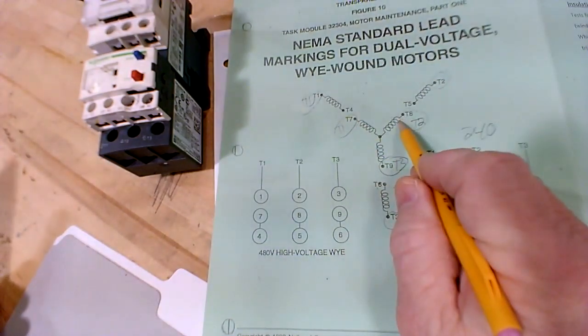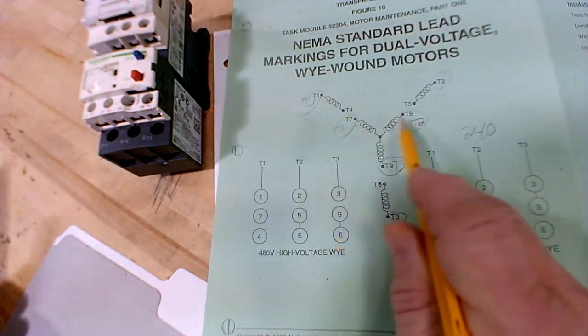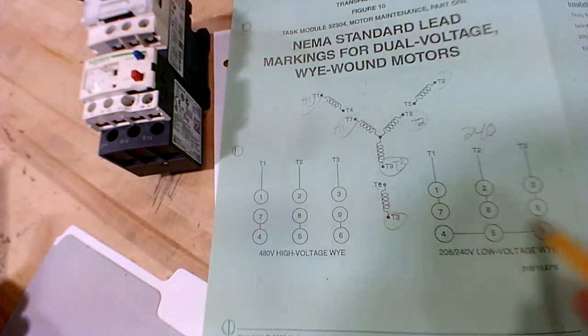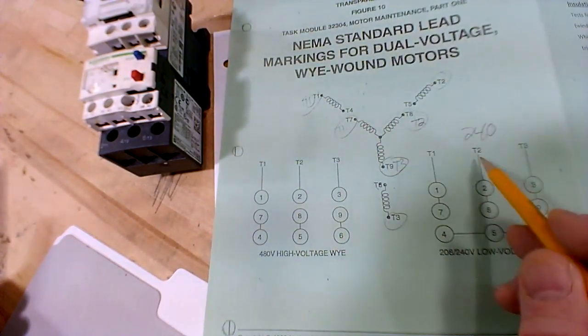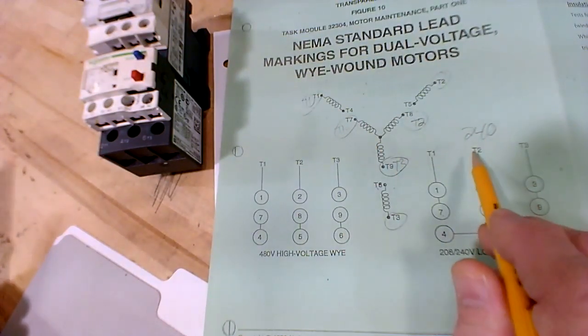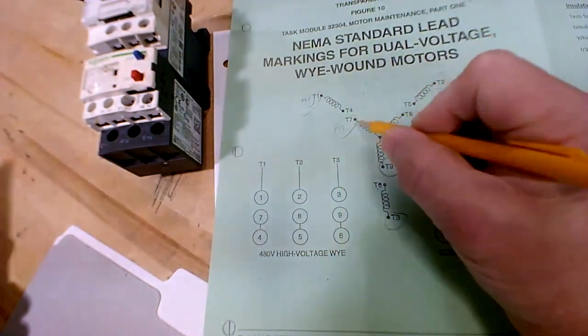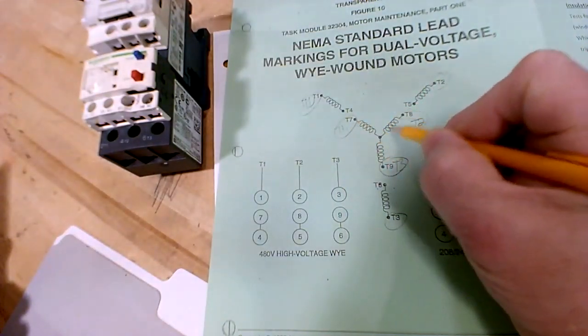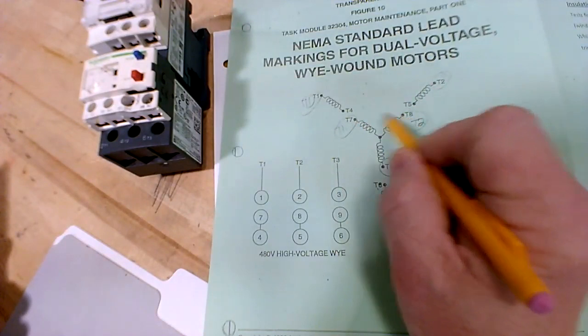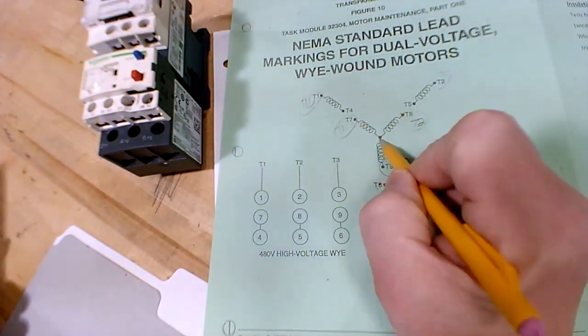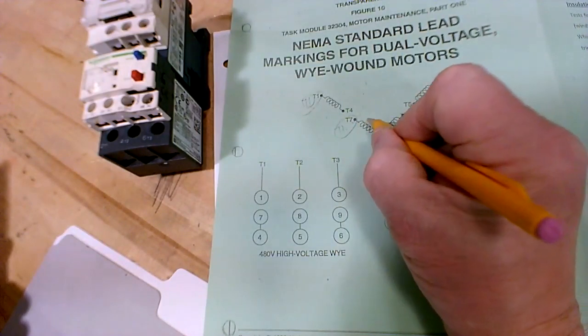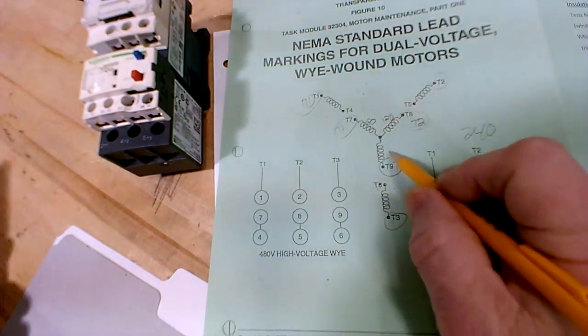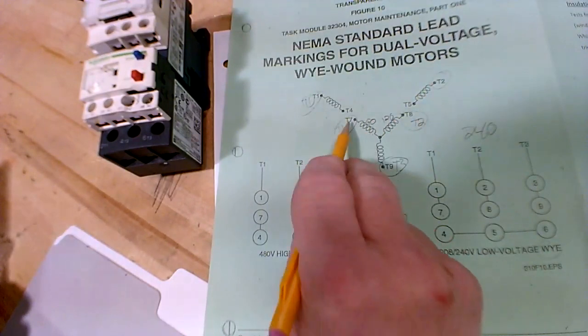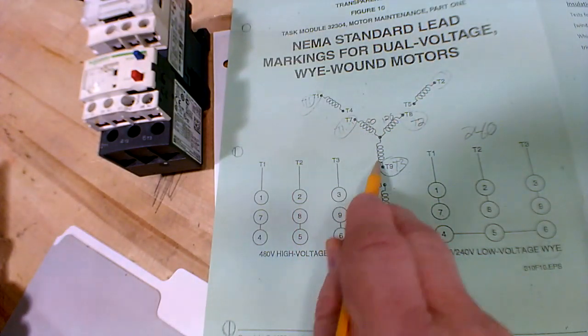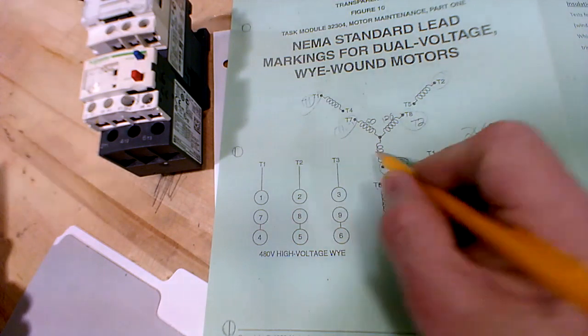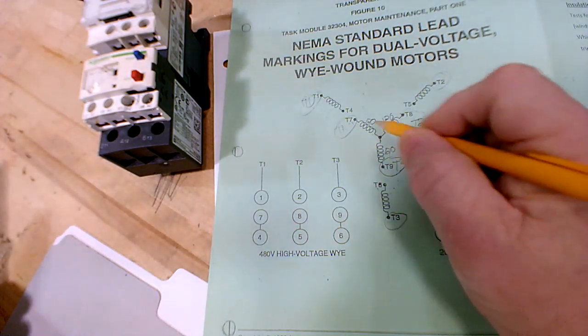So right now, on the inner Y, if I measure from here to here, what will I measure? T1 to T2 on the inner one now, over here. What would I read? 240. I would read 240 across these. Here I've got 2 windings in series. If I've got 240 across there, how much voltage drop is across each one? 120, exactly, 120 again. Now, if I measure from here to here, what? 240, which means that I have 2 windings in series, and how much do I get on each? 120. I get 120 across those.